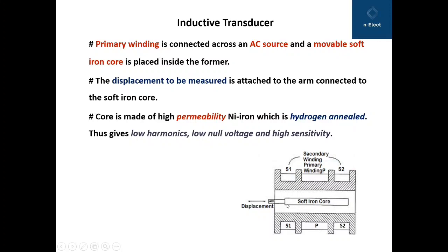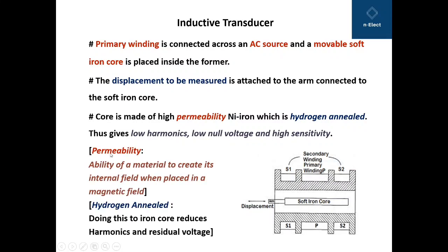This core is made up of high permeability nickel iron which is hydrogen annealed. Permeability is the property of a material to create its internal field when placed in a magnetic field. The hydrogen annealing process, when applied to the iron core, reduces harmonics and residual voltage, giving low null voltage and high sensitivity.